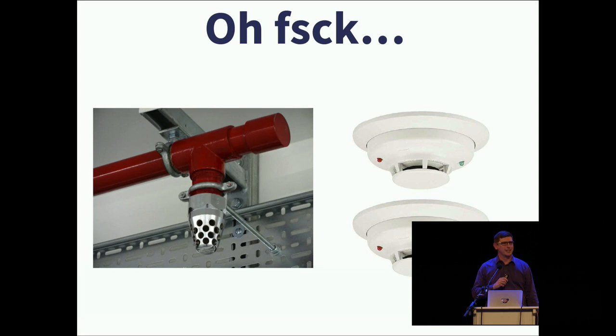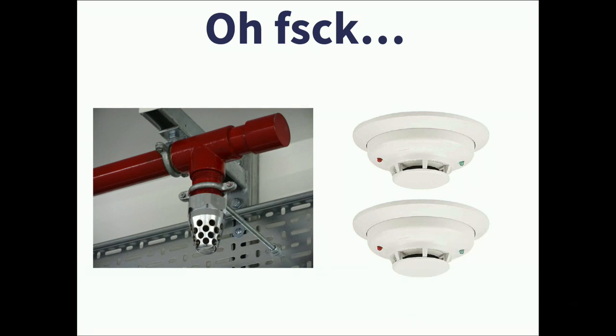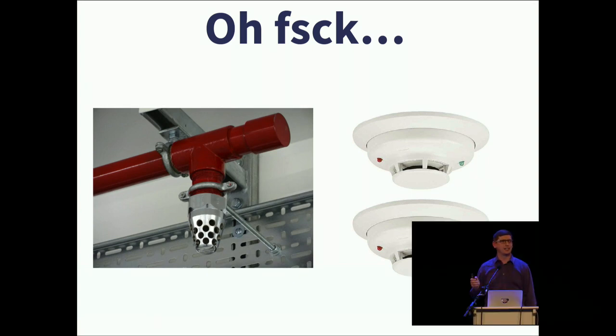But then a design element that hadn't really been taken into consideration - probably on me as part of the design team - we had the FM200 nozzles around the data center, but didn't take into consideration where the detector heads were and the pipe routing from that single cylinder of FM200. It hit two detectors, so we jumped from nothing happening to a full second stage, double knock situation - second stage alarm and activation of the fire suppression system within about a second and a half. That doesn't give you a lot of time to think about whether there's really a fire or how to respond. We've since done some very good scenario planning and analysis on this with our teams.